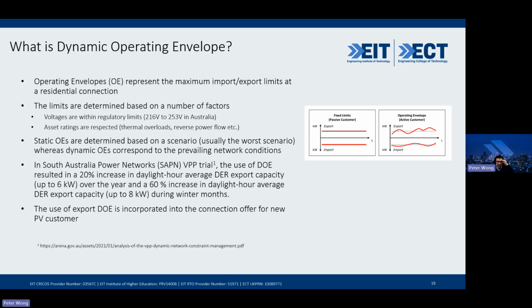We have done some trials in Australia, in South Australia for example, the utility there did a VPP trial using the DOE as a construct, and they found that they could increase the daylight hour average export from the DER, in this case rooftop solar, by about 20%, from 5 kilowatt to 6 kilowatt over the year, and a 60% increase in daylight hour average DER export capacity, up to 8 kilowatt during winter months, because winter months there is more load on the network and less generation. So the use of DOE has been proven beneficial, and it's definitely the focus right now from an Australia perspective, because we've got more of an export problem than an import problem.